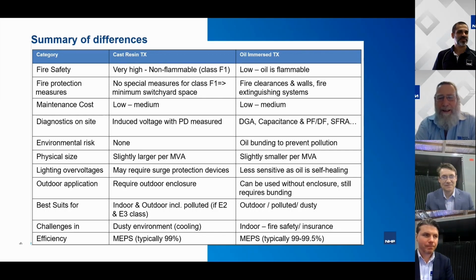Well, it's interesting because one of the comments that I hear quite often is, oh, well, cast resin transformers aren't quite as efficient as oil. And it's true. And the minimum efficiency performance standard caters for that. But you've also got to put it in perspective. So if we're talking about 1,000 kVA, an oil transformer, its minimum efficiency is 99.27. For a dry type, 99.03. So they're still both over 99% efficient, and the difference between them is not that great.